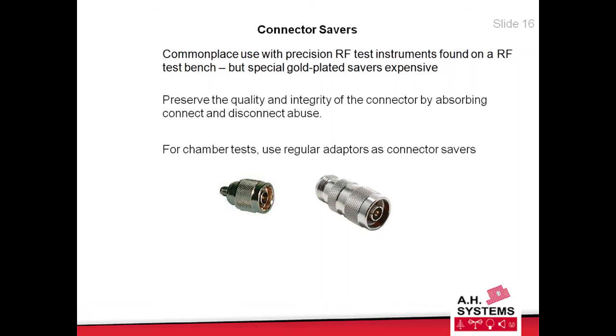So if it was my test lab and the warranty was long since gone, on that metal plate we call the bulkhead, I would put an N-type through, and then I would put on, can you see the N to SMA connector there, adapter? I would put that on both sides of that, and I would mark them with a bead of paint to make sure they haven't been undone, and to discourage others from doing it. They'll see that and they'll say, ooh, maybe I shouldn't take that off. But there's some very low-cost solution to the problem of wear and tear on an older EMC chamber.